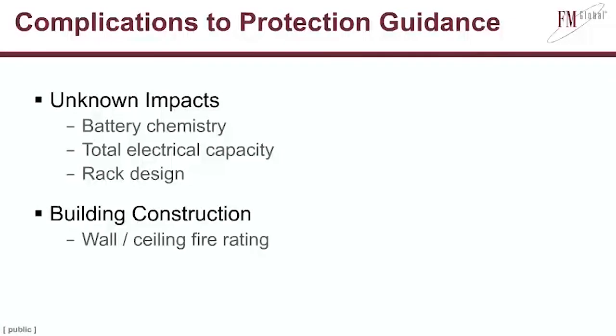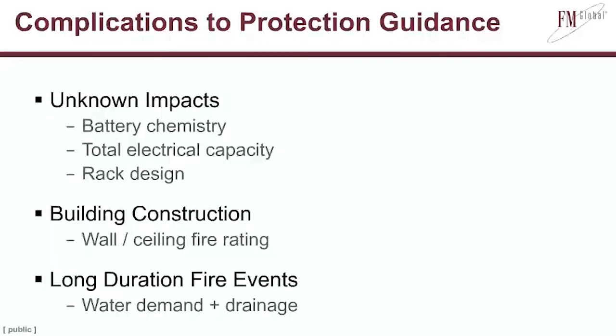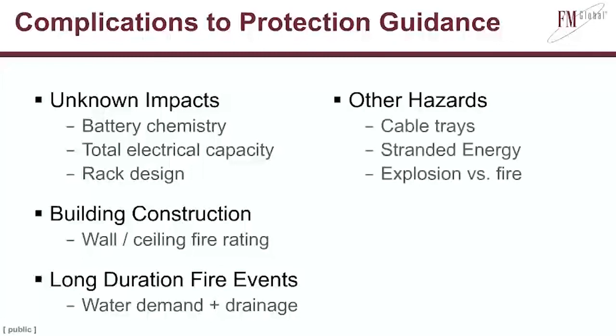There also needs to be a holistic concept of protection, because now you have fires that could be fairly large inside of a room, so you need adequate fire ratings for your ceilings and your walls. I've seen different guidance ranging from 1 hour fire rated to 2 hour fire rated. You also have to realize that these can be very long duration fire events, sometimes exceeding the standard 60 to 90 minute water durations that you'd expect for a lot of our occupancies. And when you do that, particularly if it's an occupied facility, now you have to worry about drainage for all of that water.